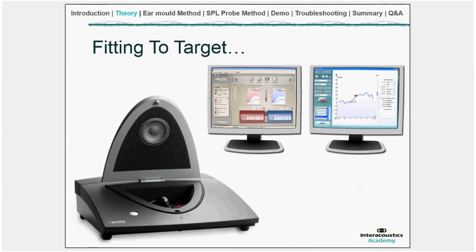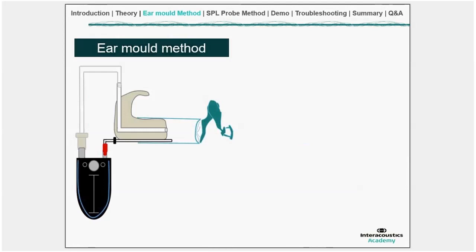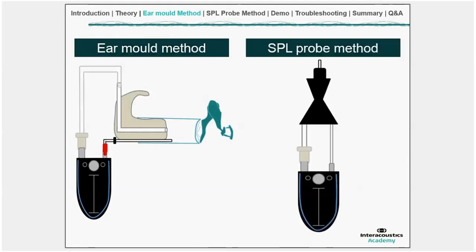There are two methods for recording the RECD. The most popular in the literature is the ear mould method — the gold standard — because it accounts for the occluded ear response with the patient's own ear mould in position. The second is the SPL probe method, which is becoming very popular. Clinicians often use it when the ear mould method isn't possible, as it's easier to perform and less susceptible to the errors the ear mould method can cause.